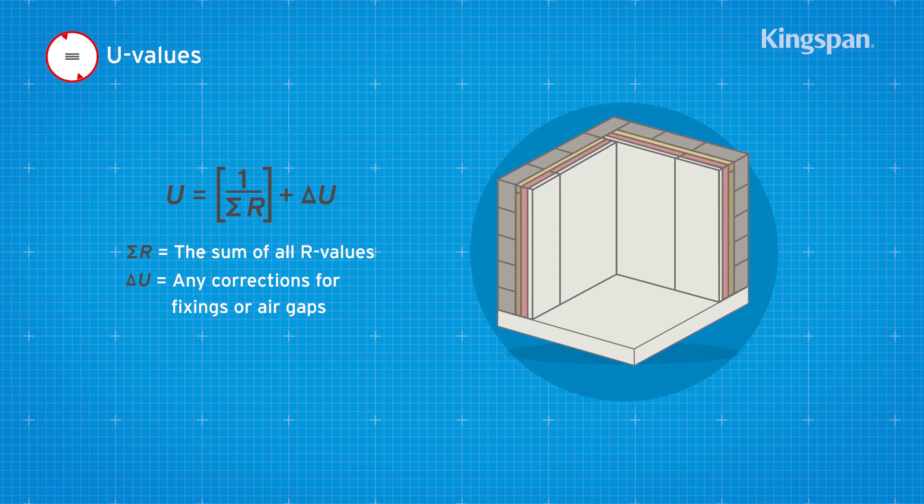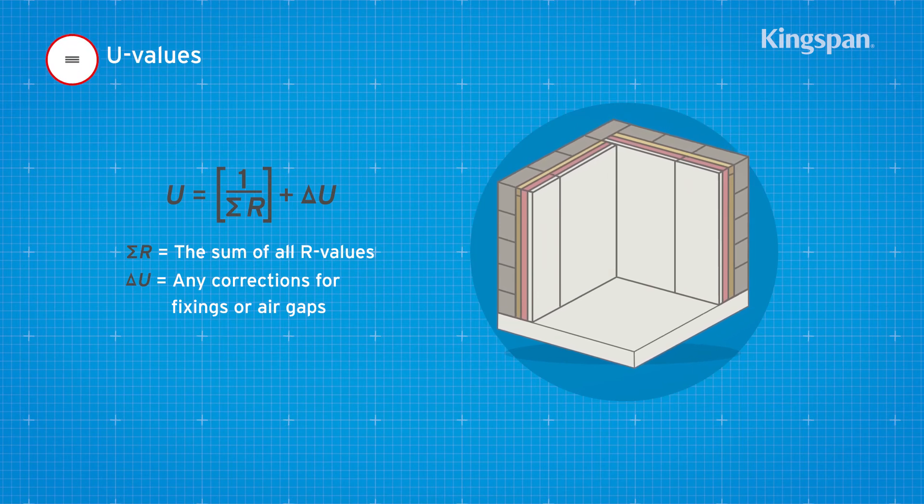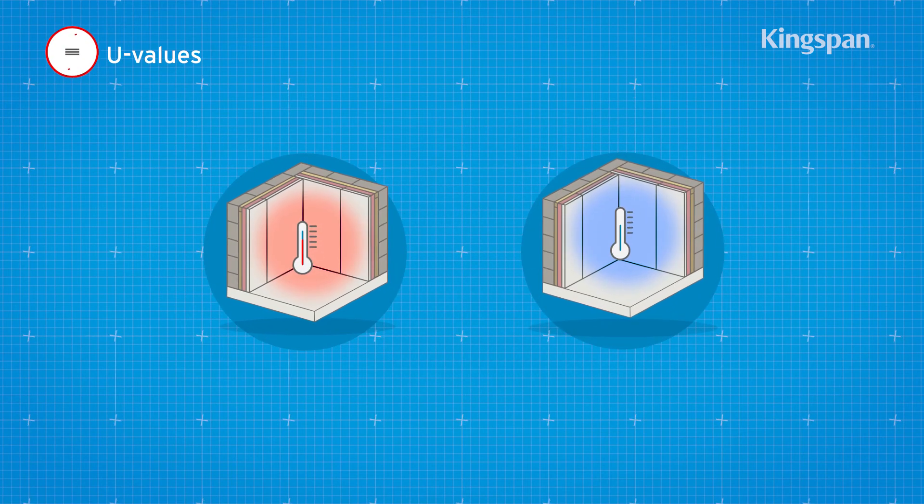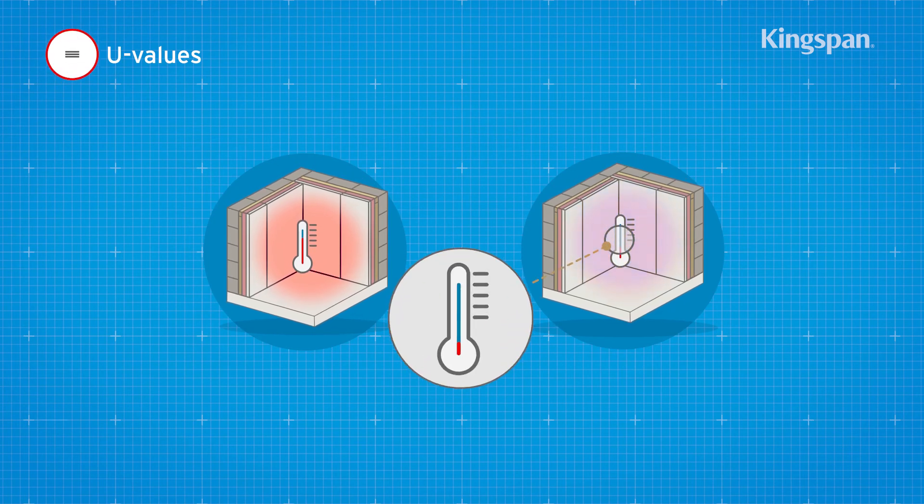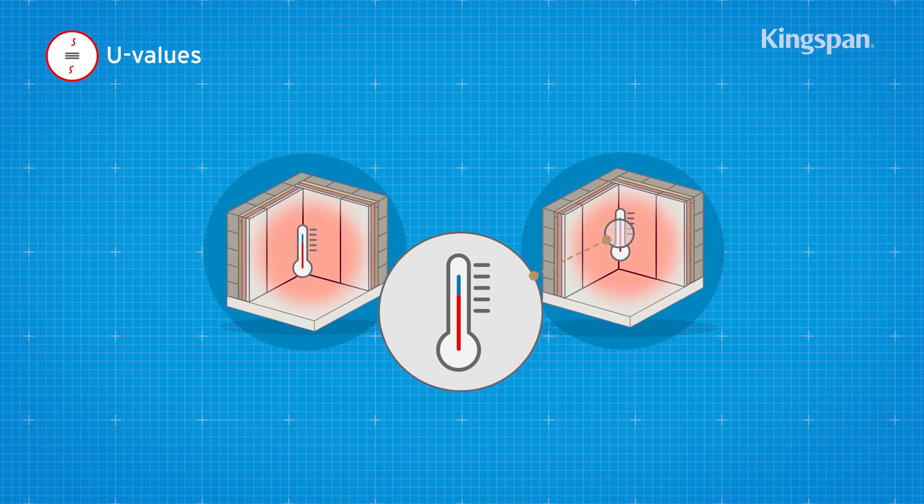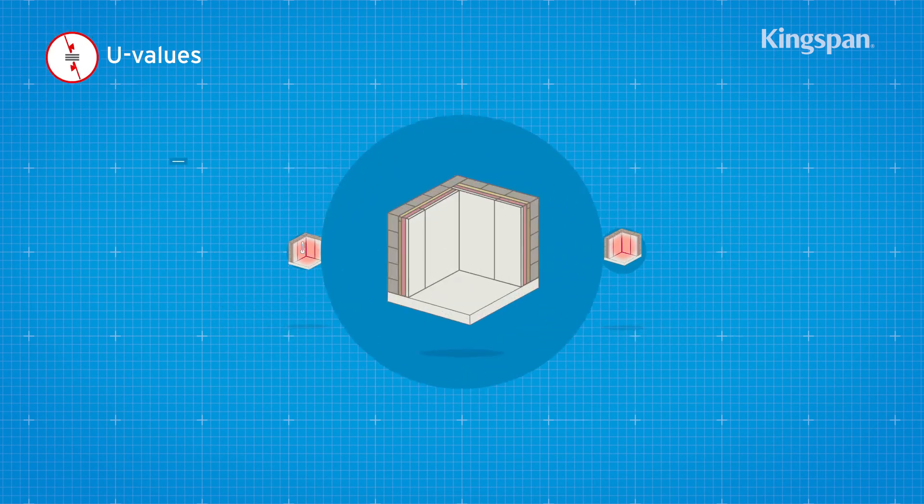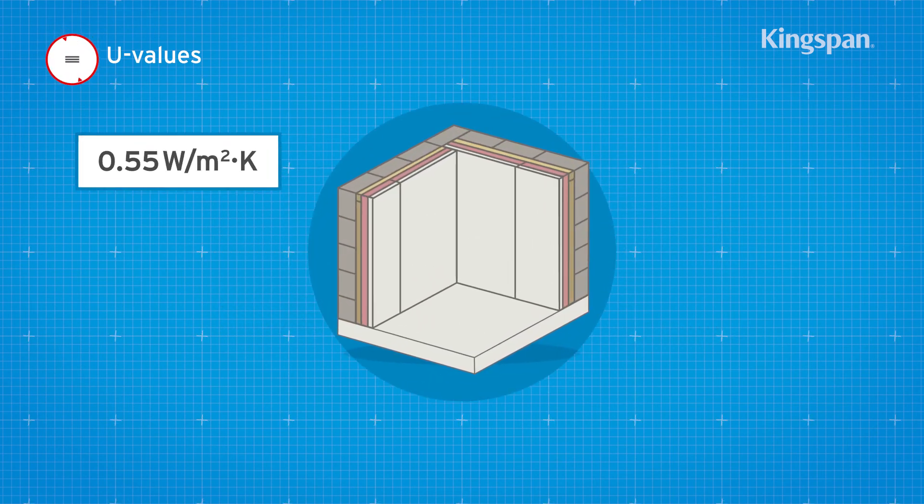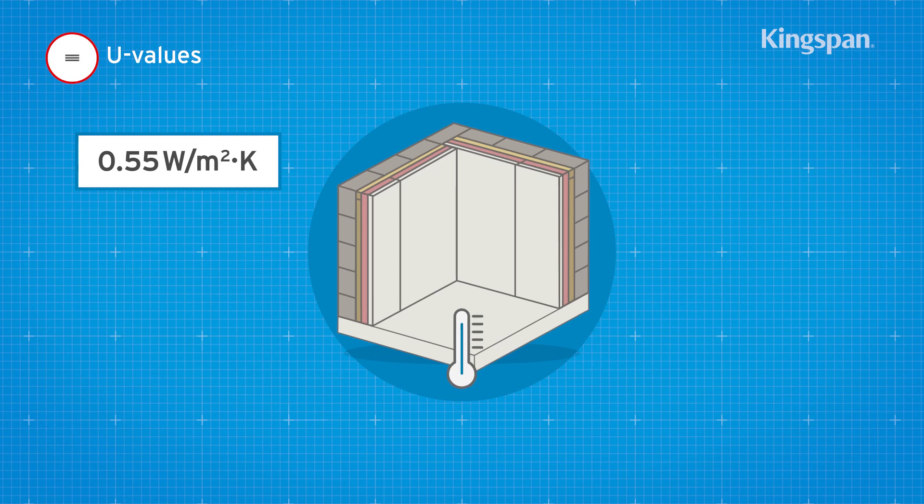In units of watts per meter squared Kelvin, the U value shows the ability of an element to transmit heat from a warm space to a cold space in a building and vice versa. It's also the figure you need to work to when meeting building regulations or standards.